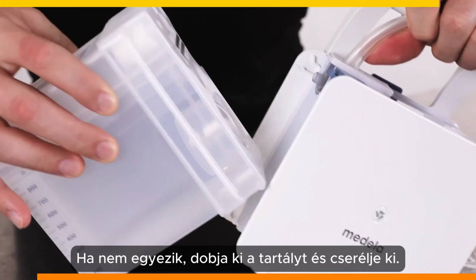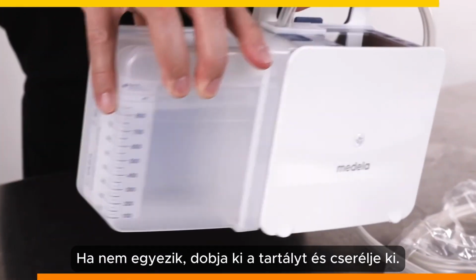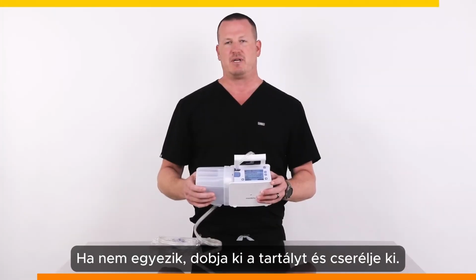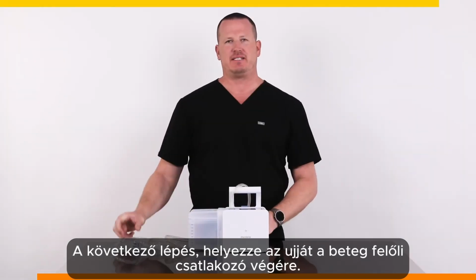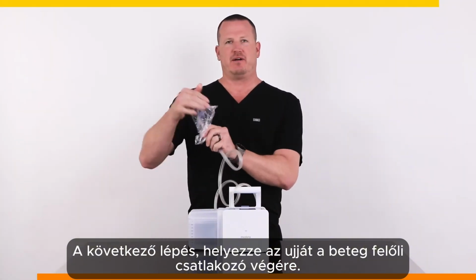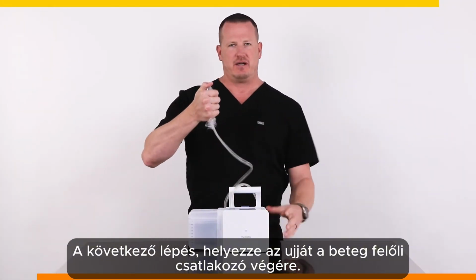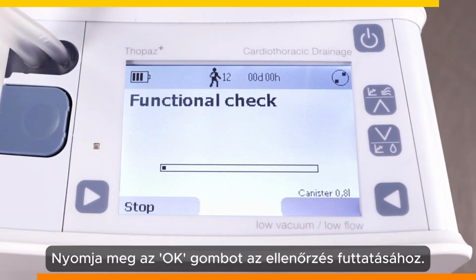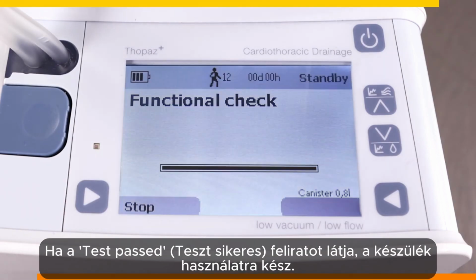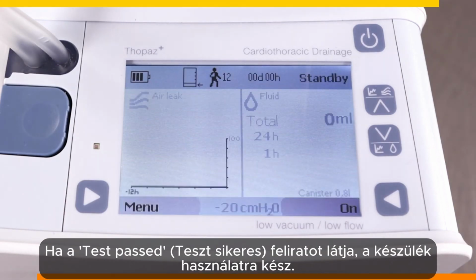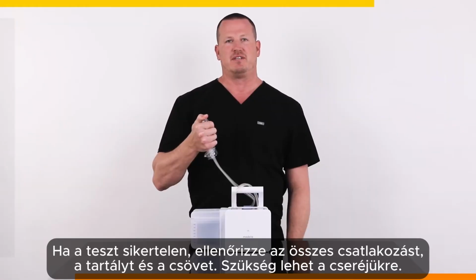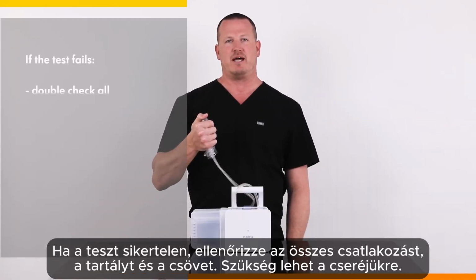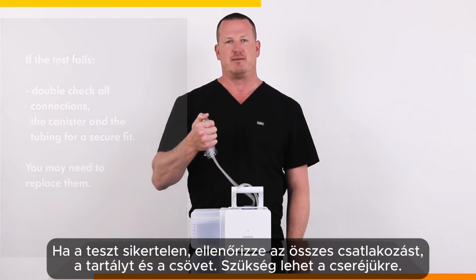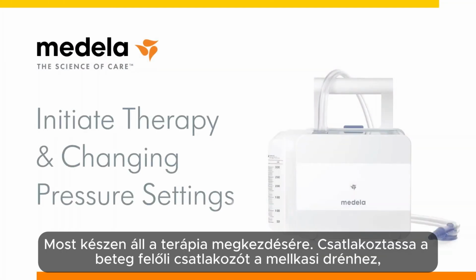If this does not match, dispose of the canister and replace with a new one before proceeding with the steps of the functional check. Under aseptic technique, place your finger over the end of the patient connector and press OK on the bottom right of the device to run the functional check. If you see the status test passed, the device is now in standby and ready to use. If the test fails, double check all connections, the canister and the tubing for a secure fit. You may need to replace them. Now we're ready to begin therapy.